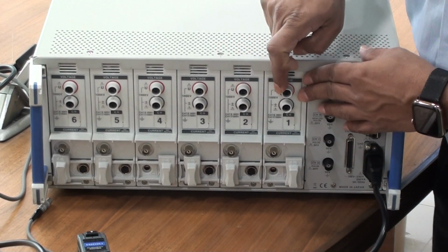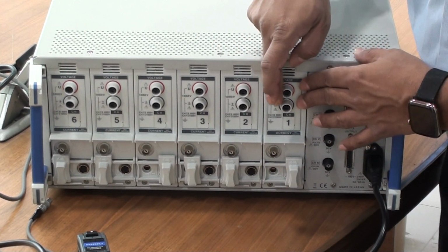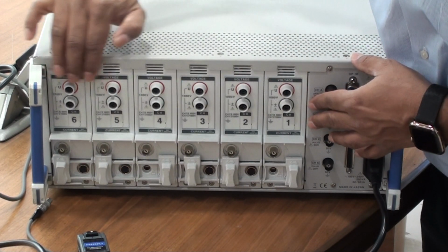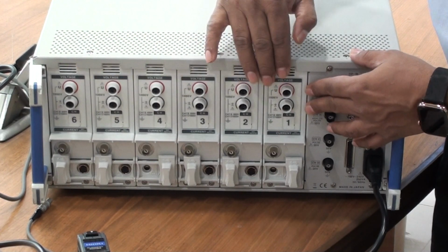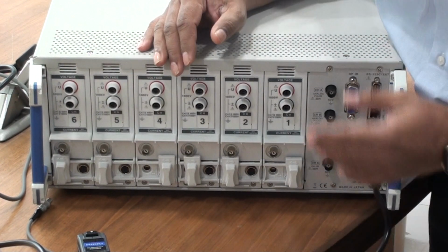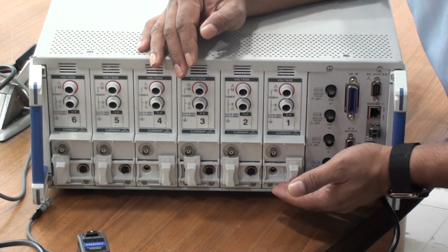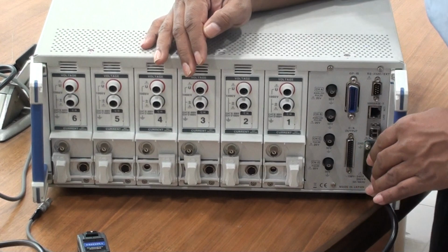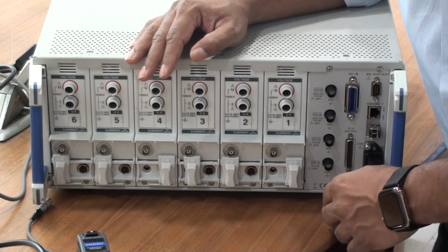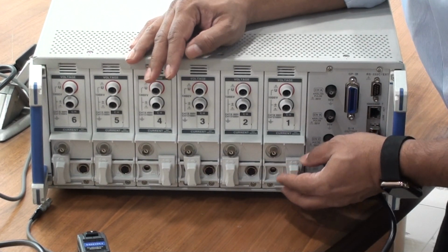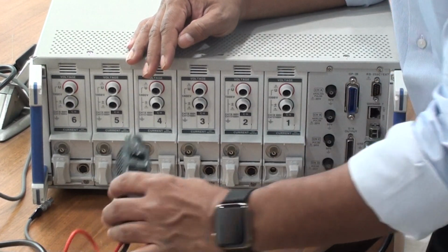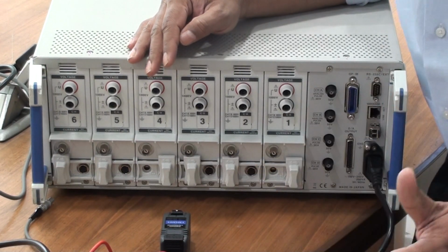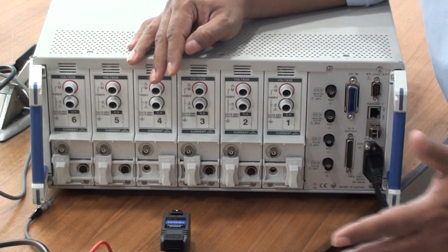This voltage here can take up to 1500 volts AC DC RMS. And similarly, all these are isolated from each other and isolated from ground. This current section here, we do not have a shunt, which constitutes a lot of noise and inaccuracy. We have a system where we could employ a clamp or a CT that will have a zero flux type of sensing, which we will come to later.